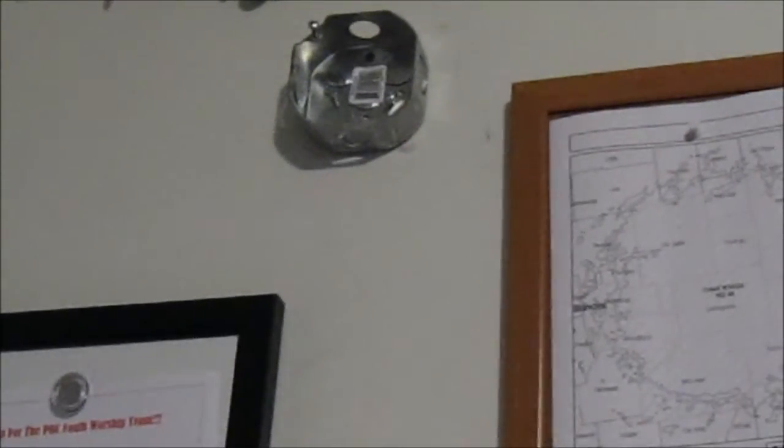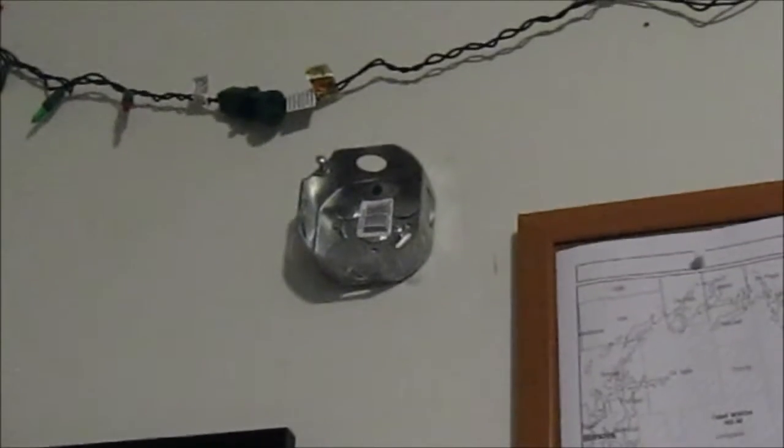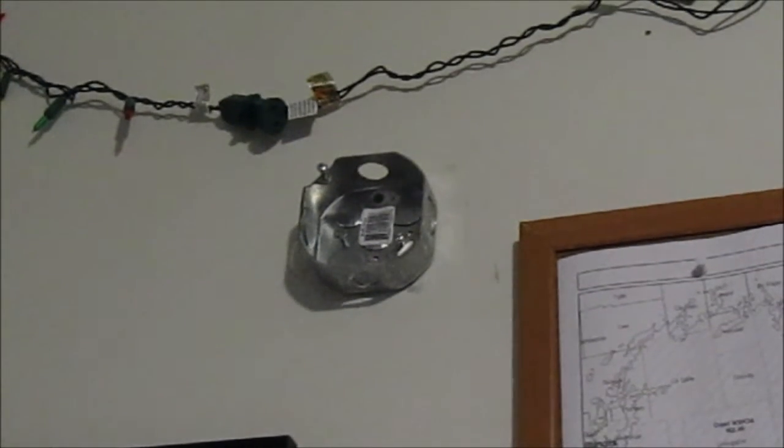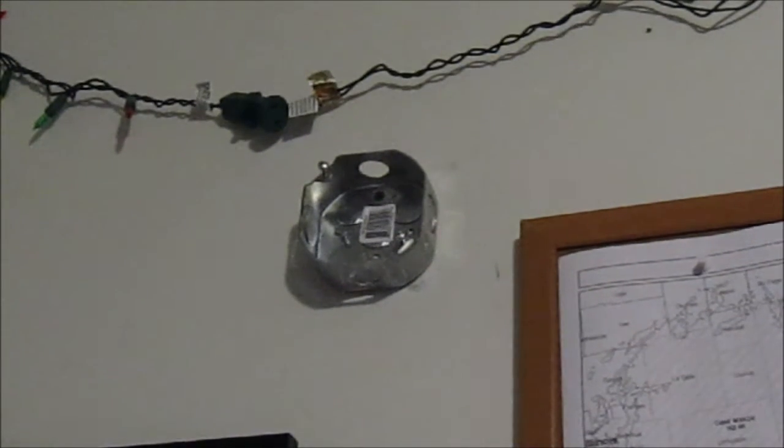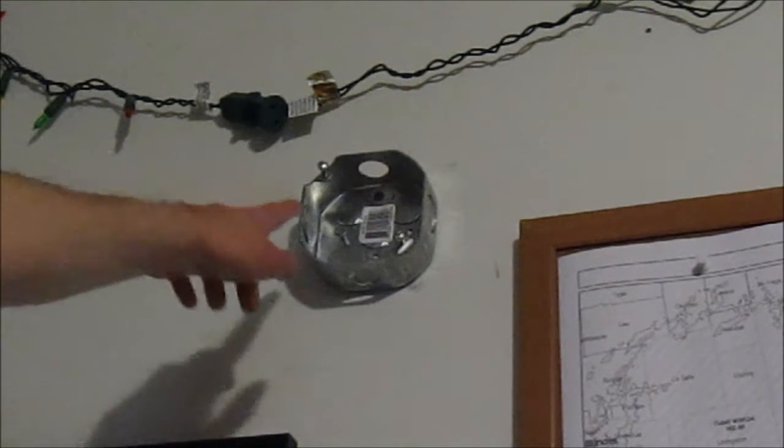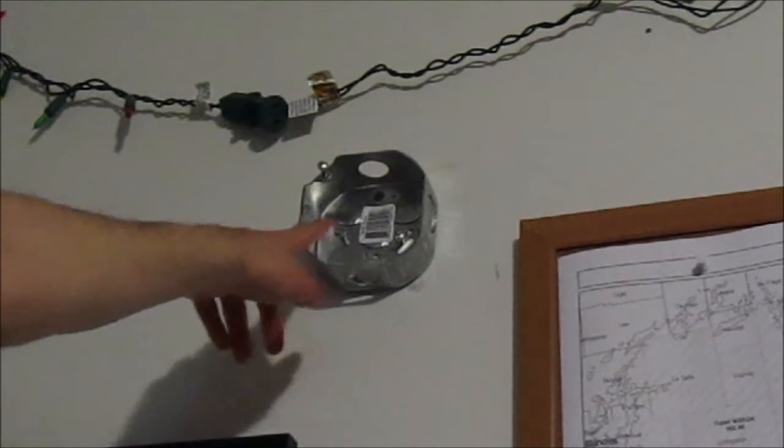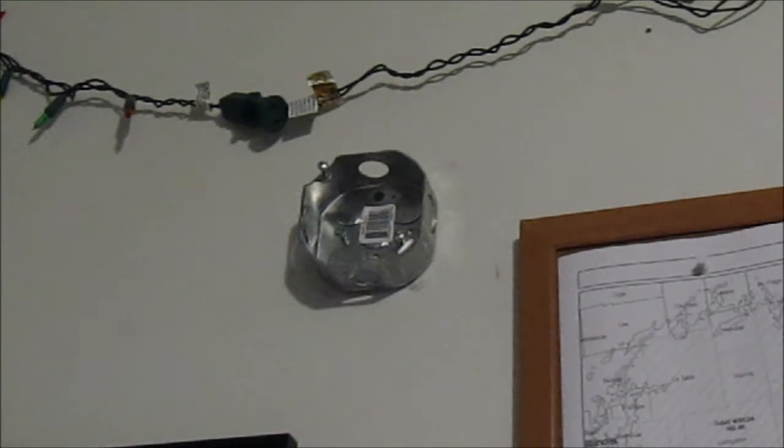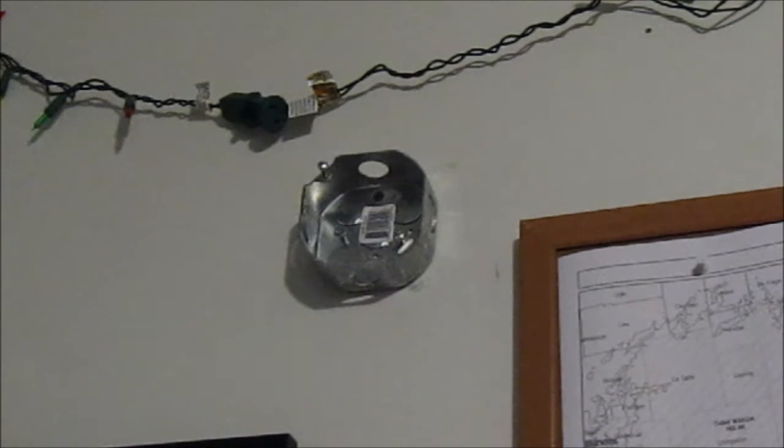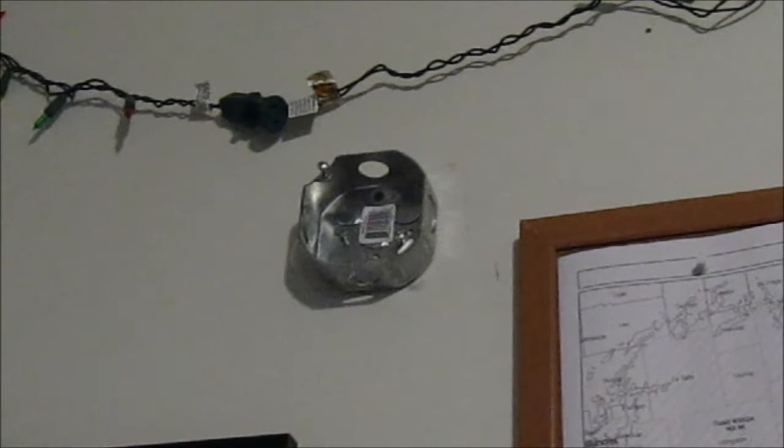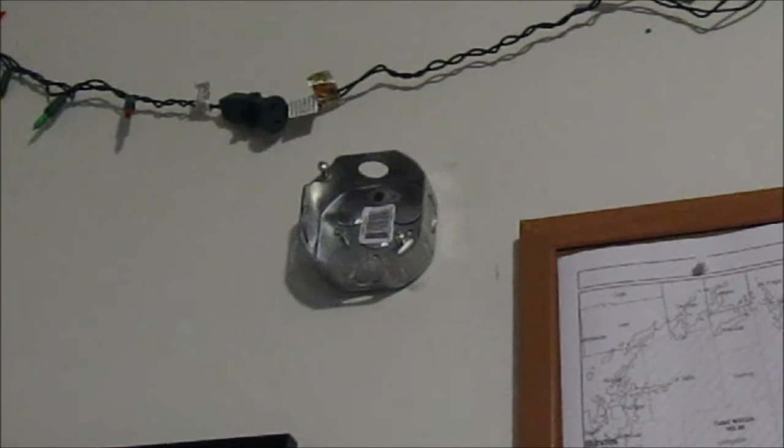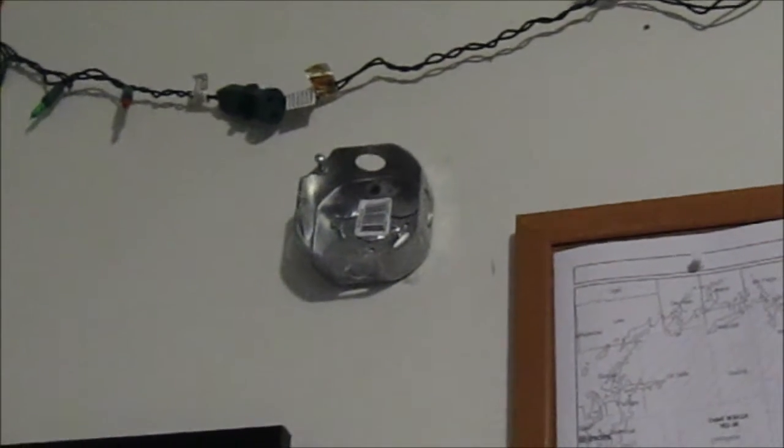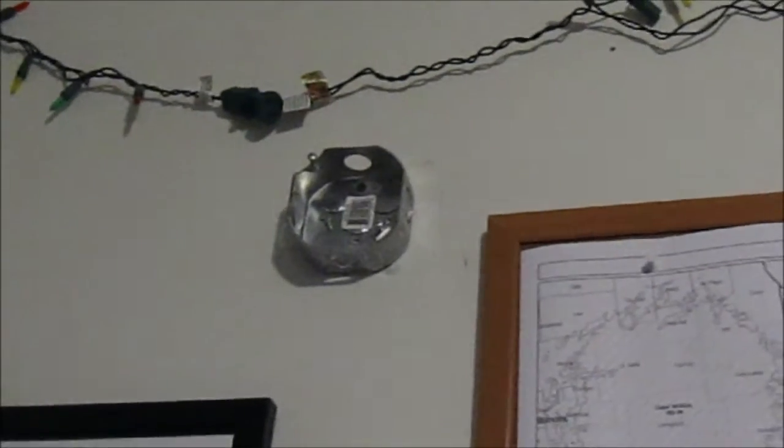Now here in the back plate, I had this for the other emergency light and it'll work for this one as well. It has two screws on it in which that's where the back plate's going to attach to. And then you can see there's a third screw right there, which is a screw that I bought because this thing lacked a ground screw and it's a metal box. So we're just going to use a simple machine screw as our grounding screw. So without further ado, we're going to attempt to get this done.